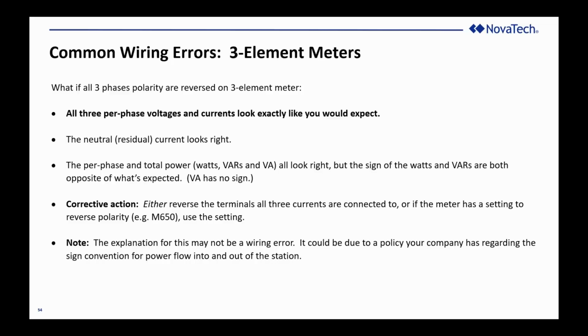Here's something we run into all the time. Some utilities want all of the power flowing into the bus to be positive and all of the power flowing out of the bus to be negative, so that the sum of the power into the bus, all of the inputs plus all of the outputs, equals 0. There's some merit to that. Other utilities want all of the power flowing from source to load to be positive and all of the power flowing from load to source to be negative. Now that's the opposite convention, but there's merit to that too. All depends what your objective is.